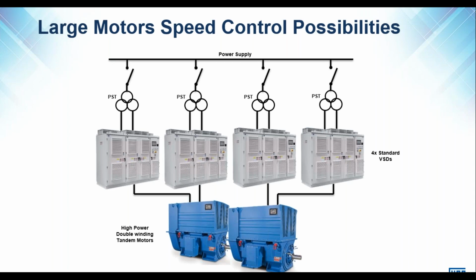All right, here's an example of using multiple VSDs for multiple motors. One example of using this type of configuration would be on a tandem load, let's say, for example, a dual pinion mill. We are able to run one motor with one VSD, one motor with the other VSD. And there's some benefit to that in terms of the phase shift transformers. We can reduce the harmonics.